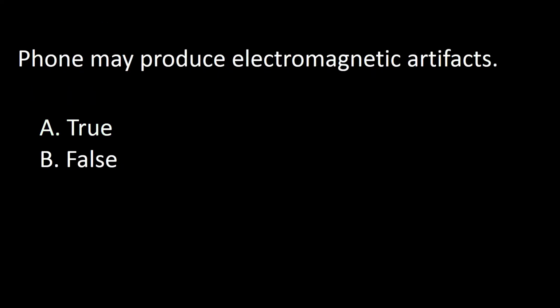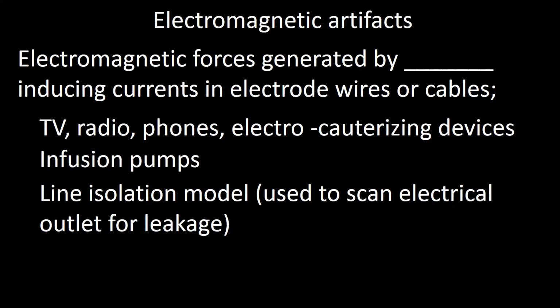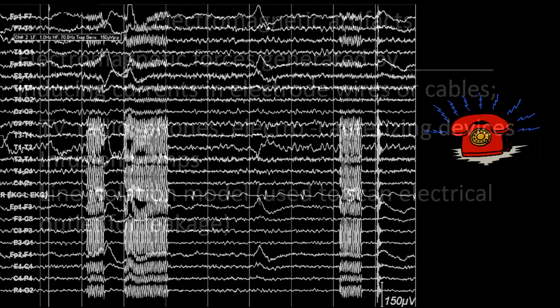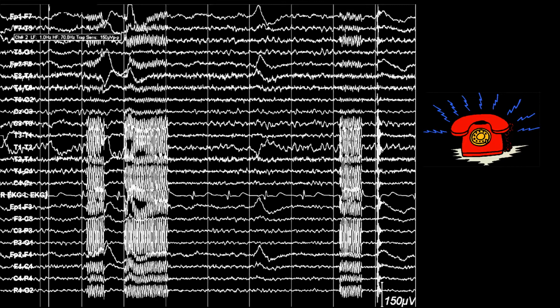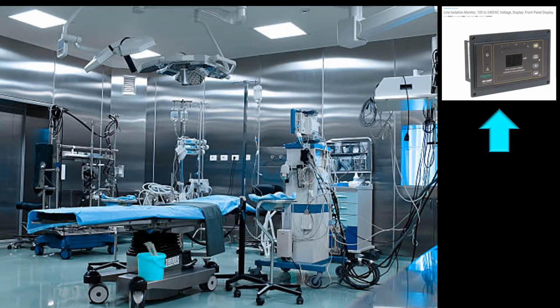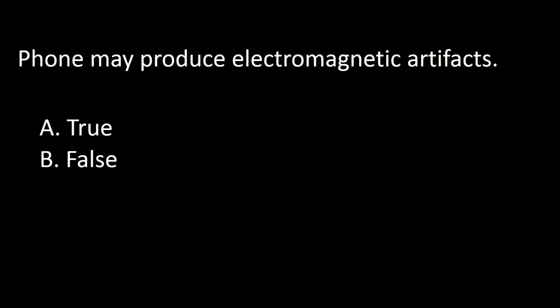Next question. Phones may produce electromagnetic artifacts. A. True, B. False. Electromagnetic artifacts are produced by forces generated by TV, radio, phones, electrocauterizing devices, infusion pumps, line isolation monitors. This is an example of phone artifact, which is either or is a combination of inductive and magnetic artifacts. Line isolation monitor, which is used to scan the outlets for leakage, can produce artifacts very similar to 60 Hz. So the answer to this question is true.